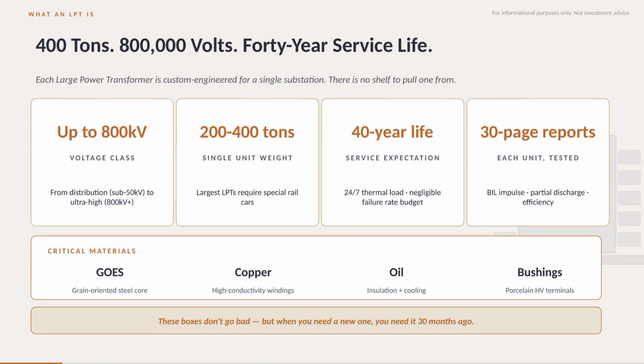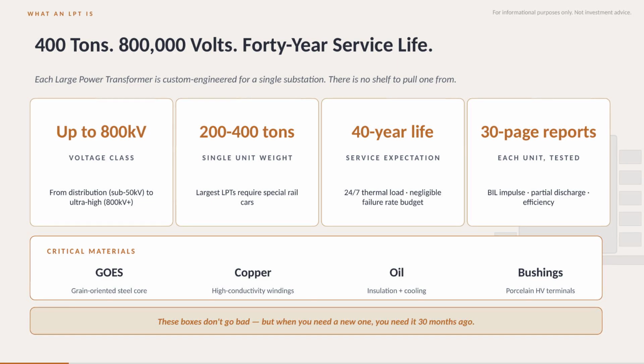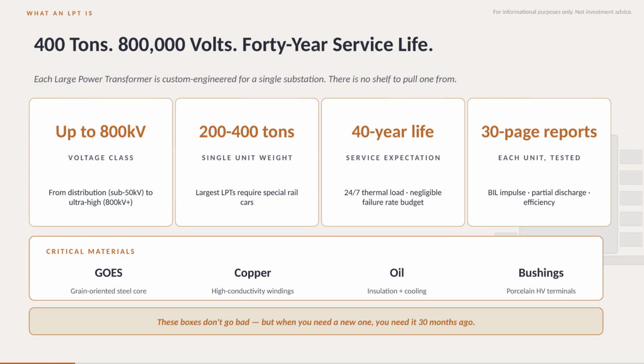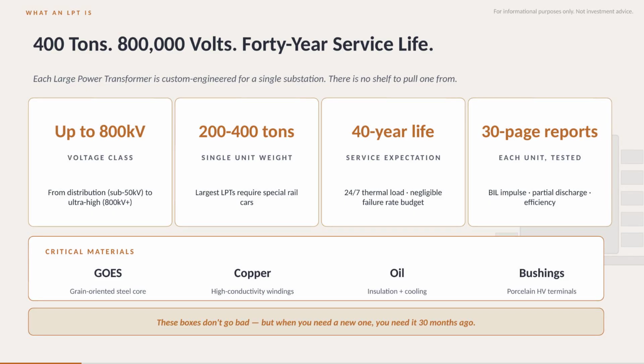You don't buy them off a shelf. Each unit is custom-engineered for a specific substation, voltage class, cooling type, BIL rating, footprint. The core is wound from a special grain-oriented steel that almost nobody makes. The windings are pure copper. Every transformer ends with a 30-page test report before it leaves the factory.